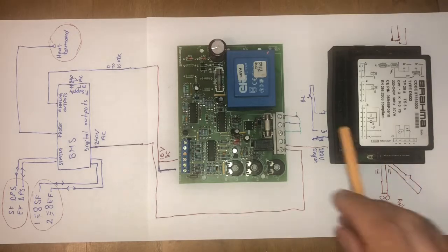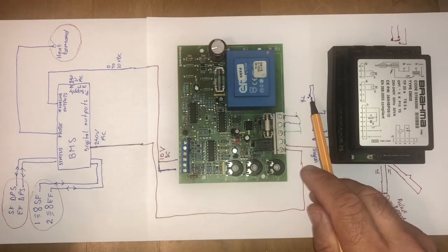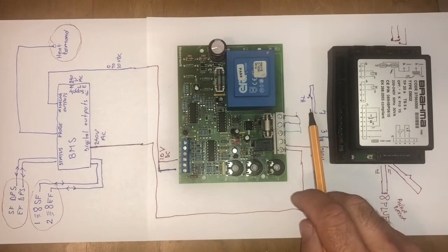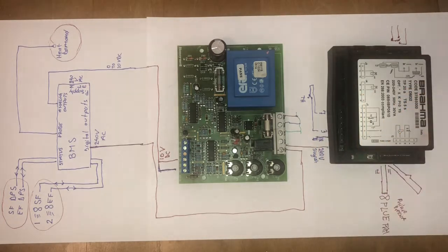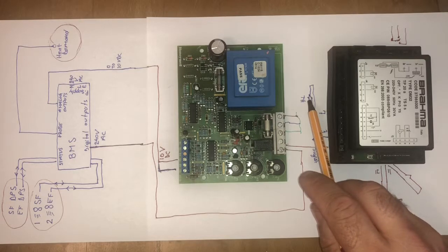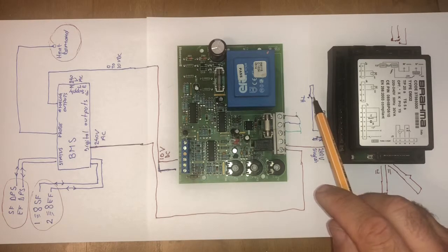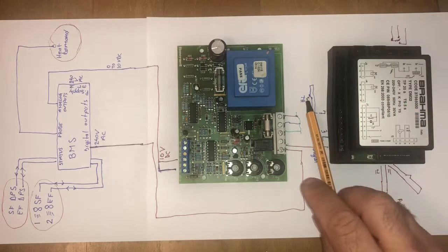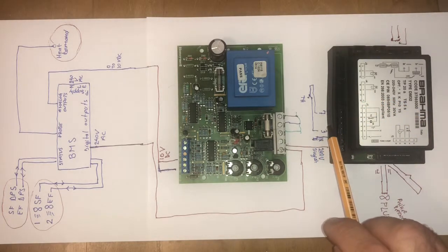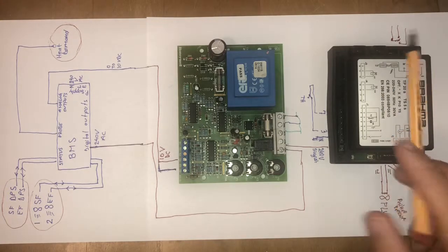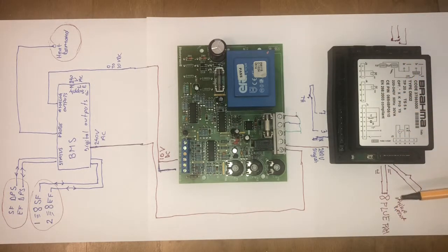The system will run until the thermostat disconnects this connection in between 7 and 3, and the Brahma will cut the heating protocol, will cut the heating. And then when the thermostat enables again, closing the circuit again between 7 and 3, the Brahma knows that it has to start the heating protocol again, and it will start again with the fan, closing circuits, the zapper, the gas valve, and the ionization probe, and then the flame will heat the store again. This is it. It is not complicated.